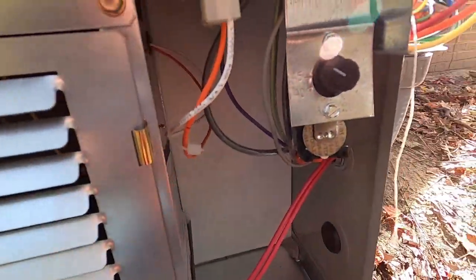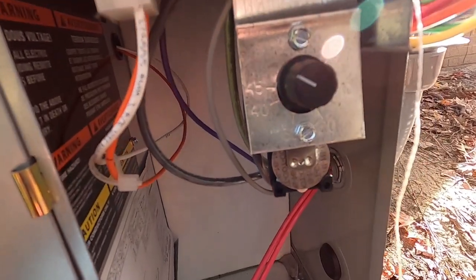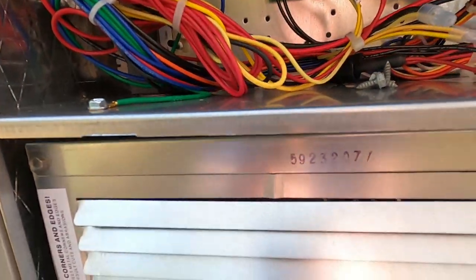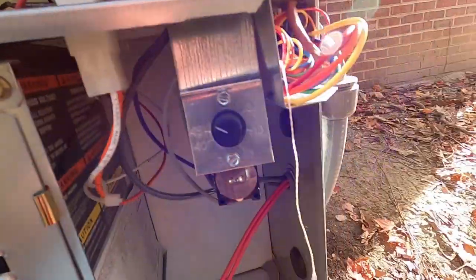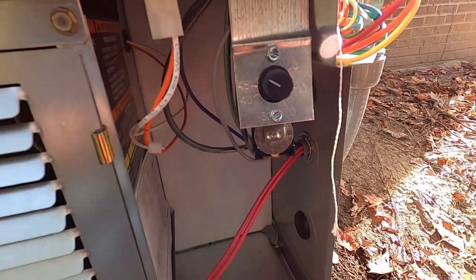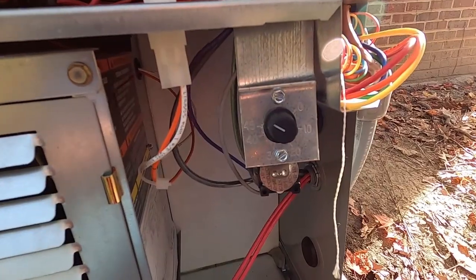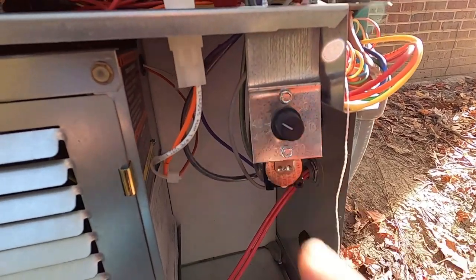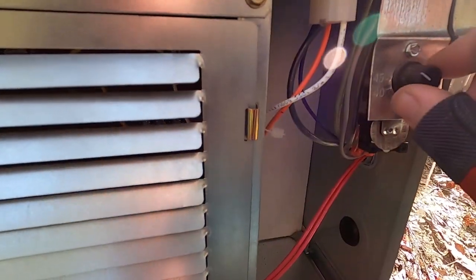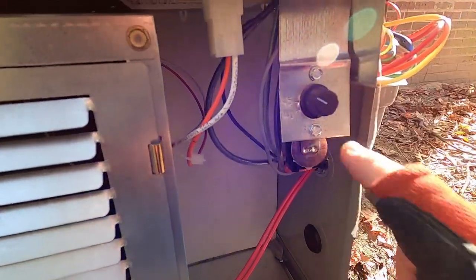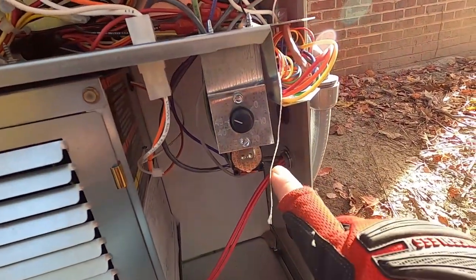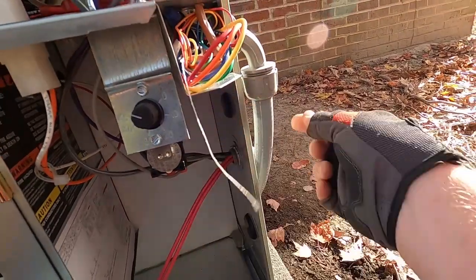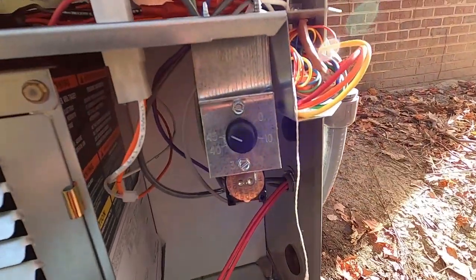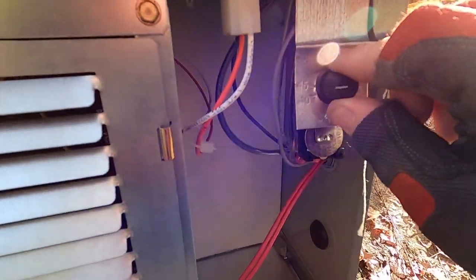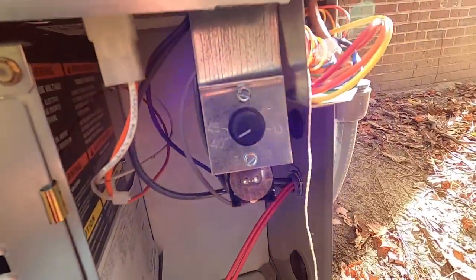And very rarely is it going to get cold inside of this electrical panel, even when it's 30 degrees, and I've seen it happen. These disc operated switches, the inside of this panel doesn't get cold enough for the auxiliary heat to come on. So I can already see we're going to have to come back and change that out and get the one that has the thermocouple on it, where I can run it outside where it's actually out into the air. But we typically will set those at about 40 degrees.